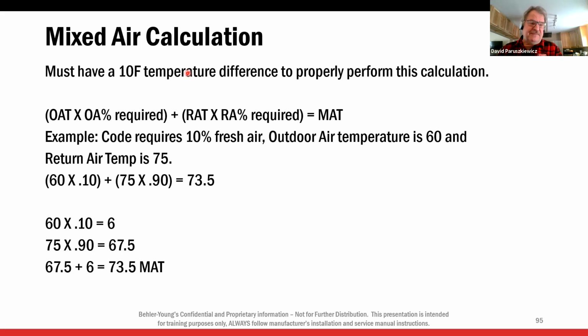So what's 10% of that? Okay, that's how I'm going to figure out what my fresh air percentage is. So we figured out we need 10% fresh air, right? So in our particular installation, we need 10% fresh air. Outdoor air is 60, return air is 75.